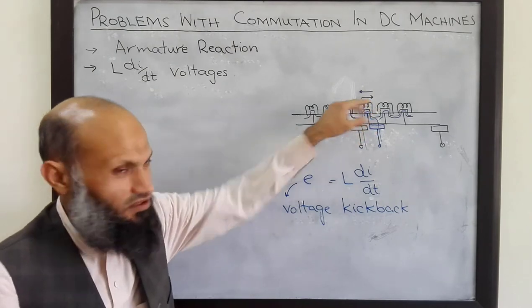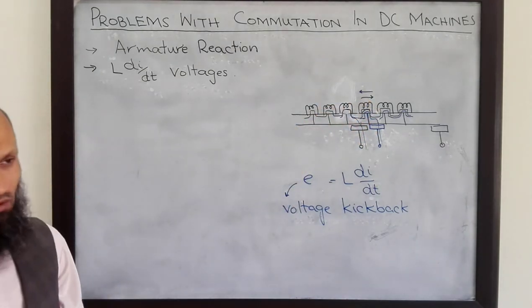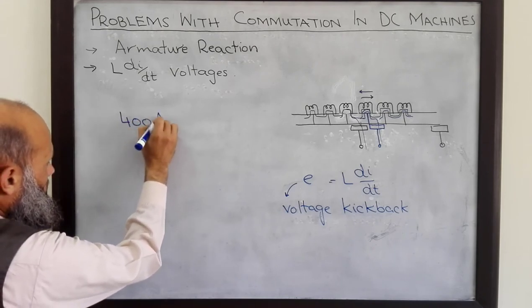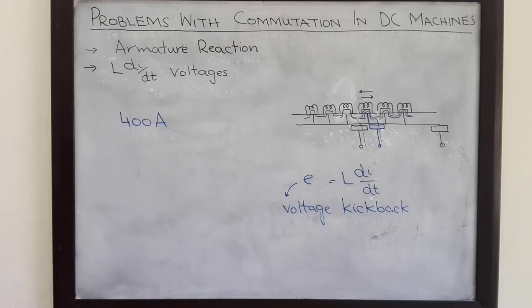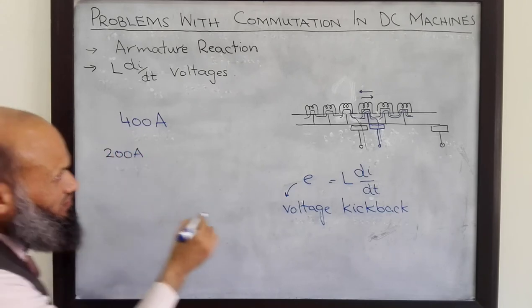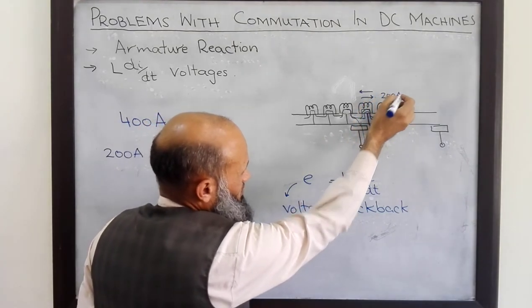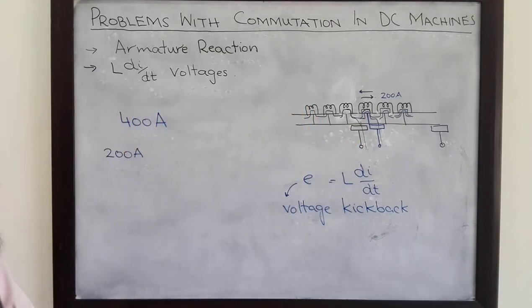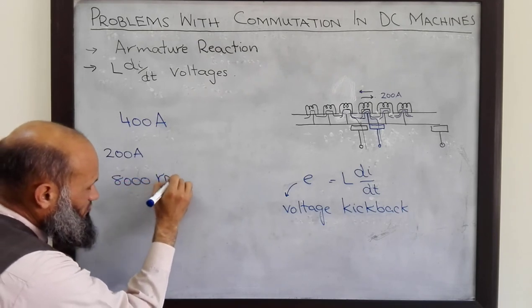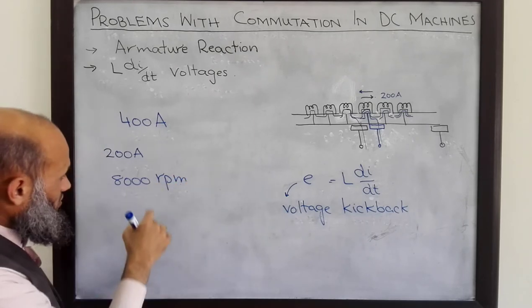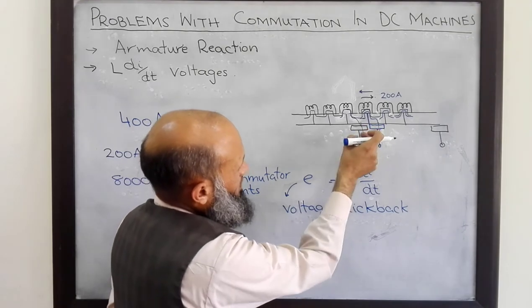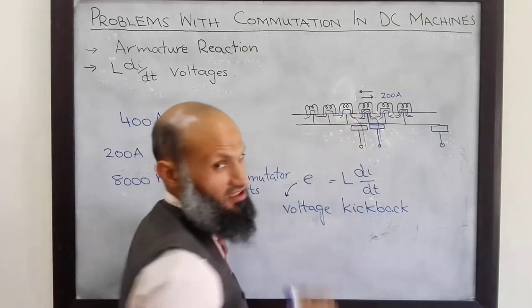To give an idea about these voltages, let's demonstrate with some numerical values. Consider a DC machine with 400 amperes and two parallel paths, so each parallel path carries 200 amperes. We assume this machine is working at 8000 RPM with 50 commutator segments. How much time will it take for the brush to move from one commutator segment to the next?